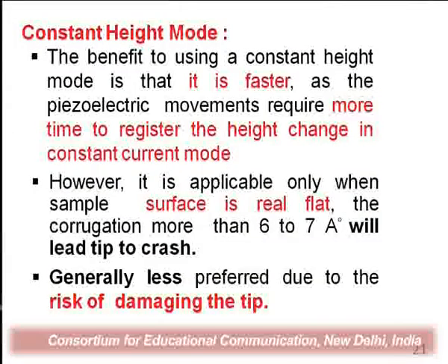The benefit of using the constant height mode is that it is faster, as piezoelectric movement requires more time to register height changes in the constant current mode. However, it is applicable only when the sample surface is really flat. This constant height mode applies only for samples having a smooth surface, where the height variation is 6 to 7 angstrom, otherwise the tip will be crushed. Generally it is less preferred due to the risk of damaging the tip.